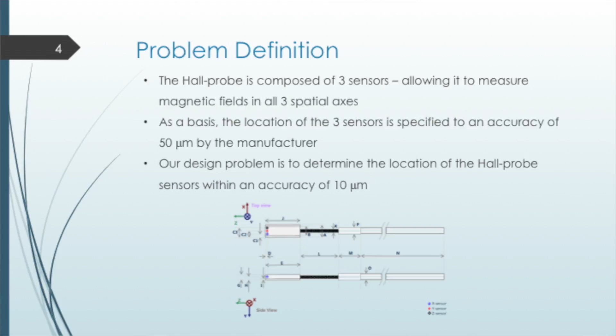So the Hall probe itself is composed of 3 sensors, and this allows it to measure the magnetic field in 3 spatial axes. So you can see from this little diagram here, I guess kind of far away for some of you, but there's an X, Y, and Z sensor mounted onto a plate. And as a basis, location of these 3 sensors is specified to an accuracy of 50 micrometers by the manufacturer. And our design problem is to determine the location of the Hall probe sensors to within 10 micrometers.